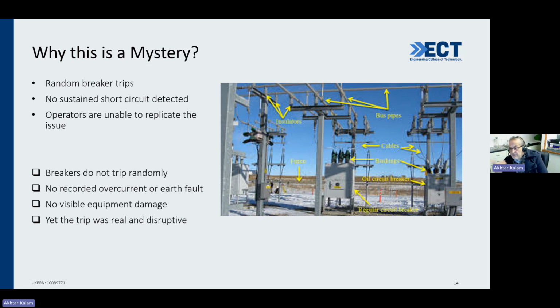The first thing is that the breaker has tripped. That itself is a mystery. It is random. You can't expect the breaker. There was no fault. The protection did not get the indication that there is a fault. The protection did not see it, so it did not send any signal to the circuit breaker. Why the hell did the circuit breaker operate? And the other thing is that operators could not replicate the issue. Remember, my friend, a real protection system is quite different from what you learn from textbooks. So my question to you: if nothing is wrong, why did the breaker open?